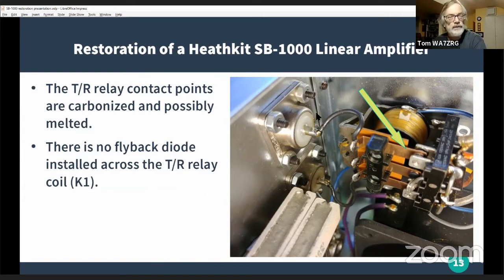The normal way of protecting against that is to put what's called a flyback diode across the coil. That inductive surge, when you try to de-energize the coil, gets sent back into the coil and tends to squelch itself out, so you don't wind up with a really high voltage damaging the semiconductor switch. So I added a diode across the coil.